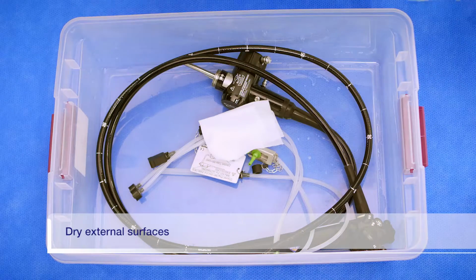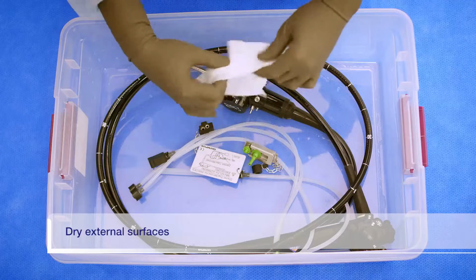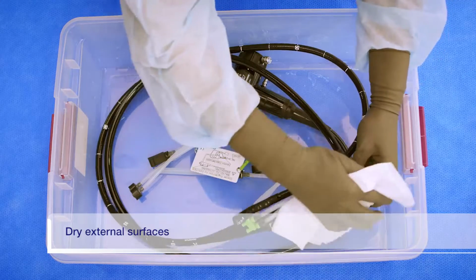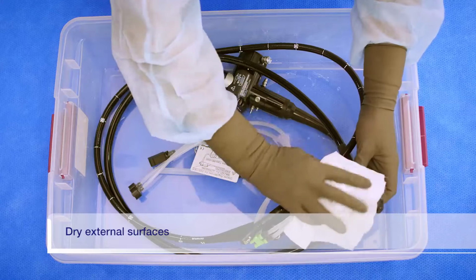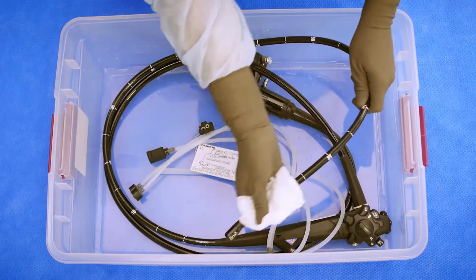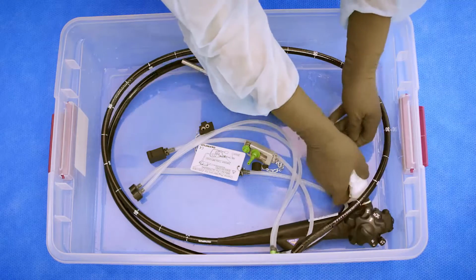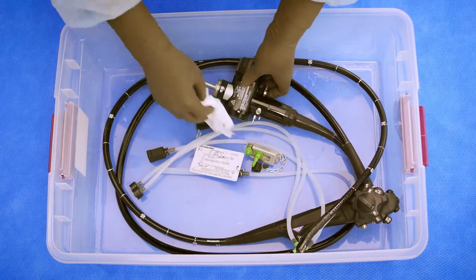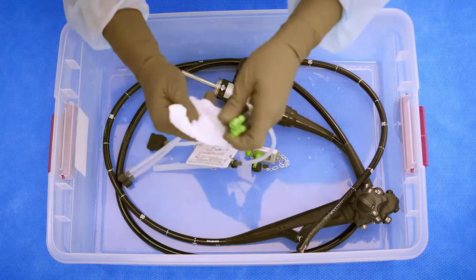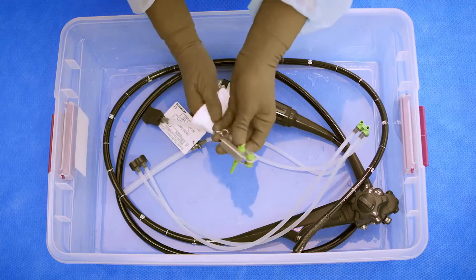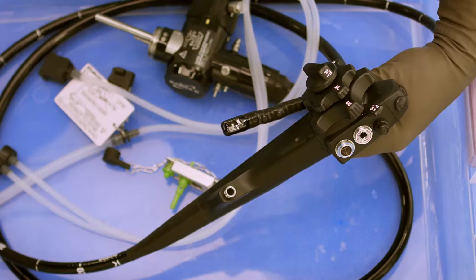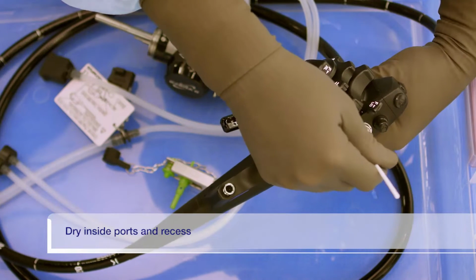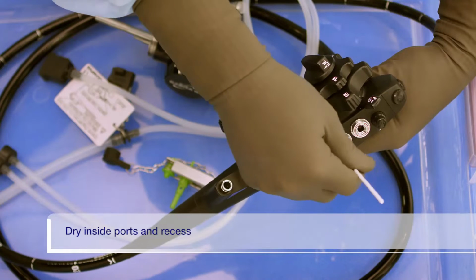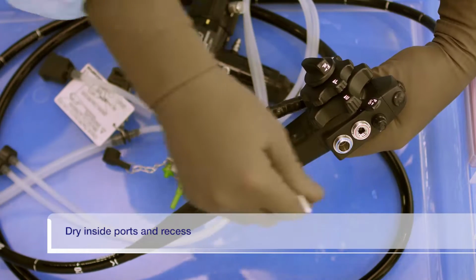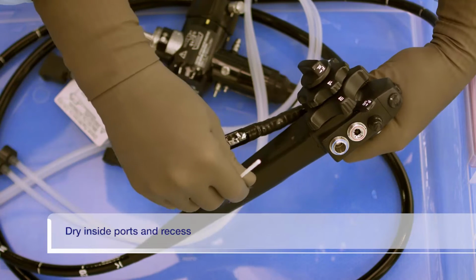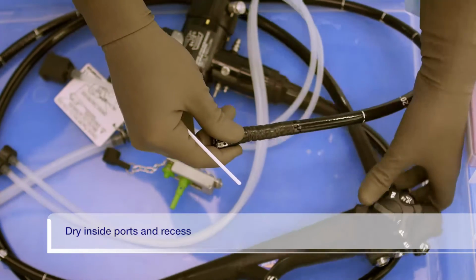Thoroughly dry the external surfaces of the endoscope, the channel plug, and the injection tube by wiping with a sterile lint-free cloth or cloths. Thoroughly dry the inside of the suction cylinder, the air-water cylinder, the instrument channel port of the endoscope, and forceps elevator recess using a sterile cotton swab or swabs.